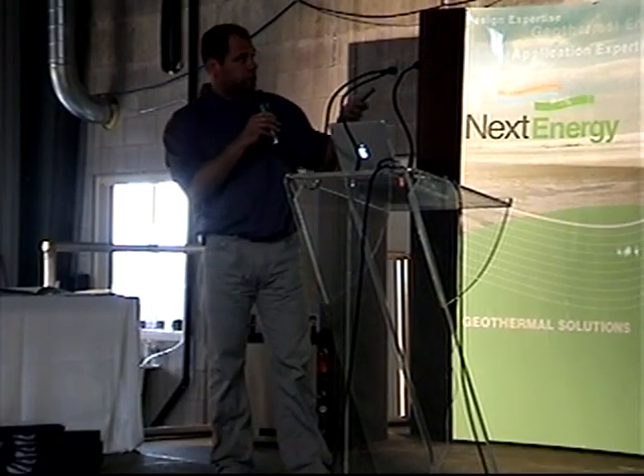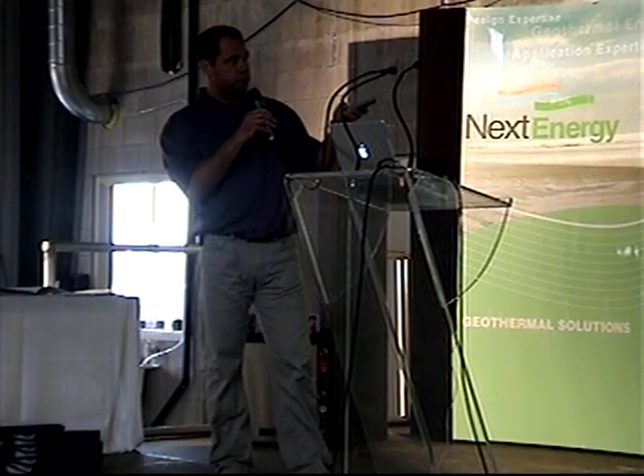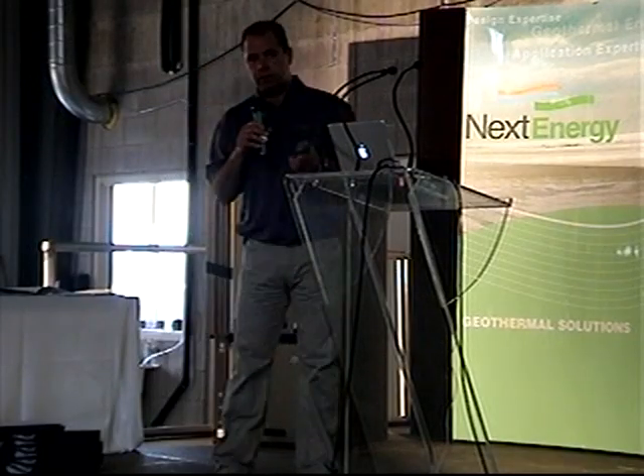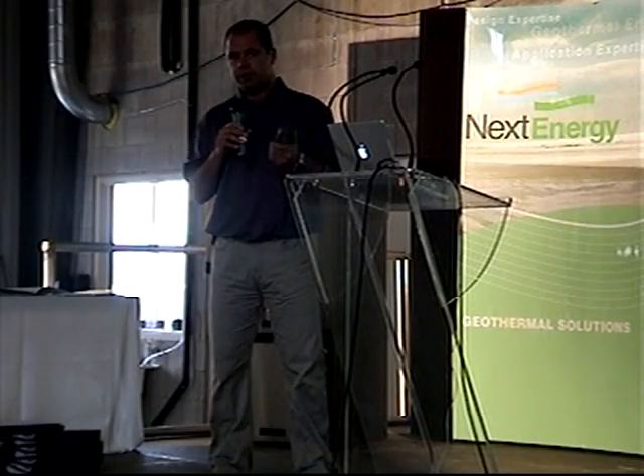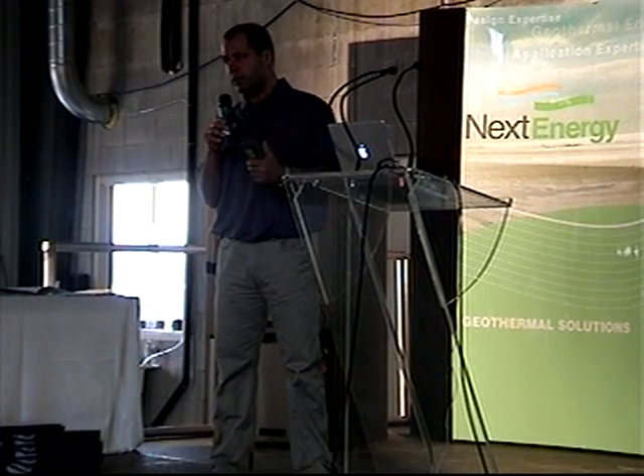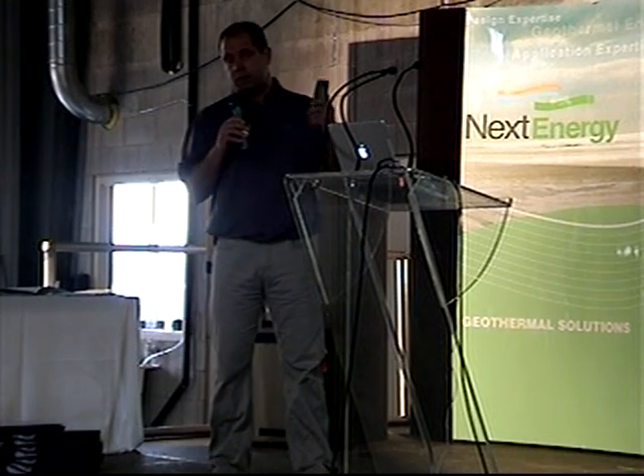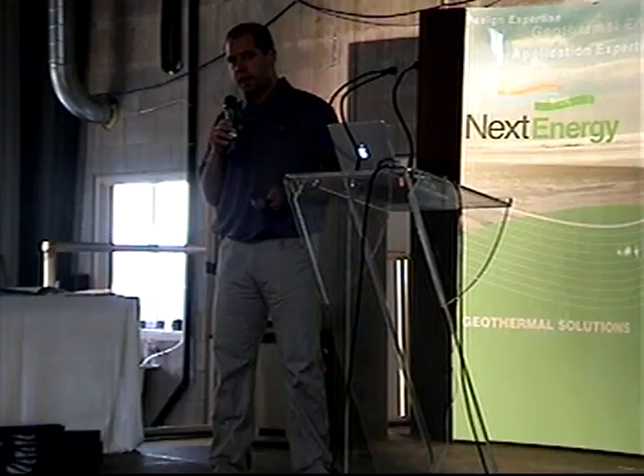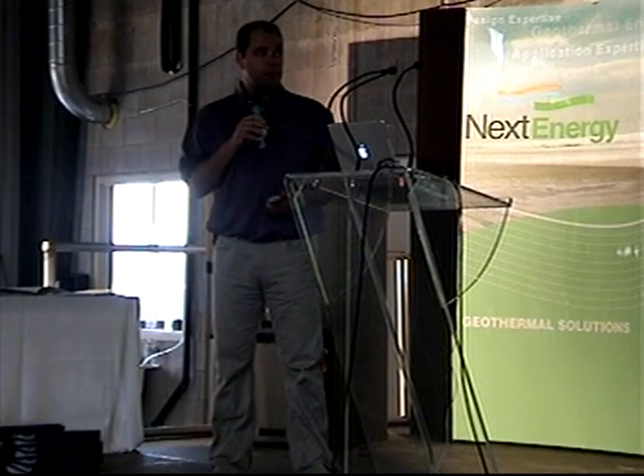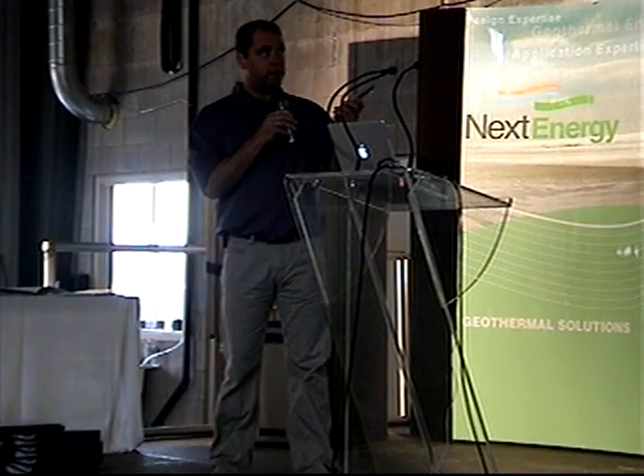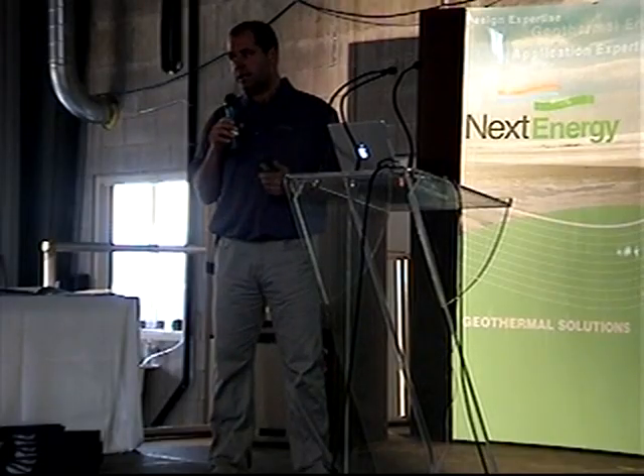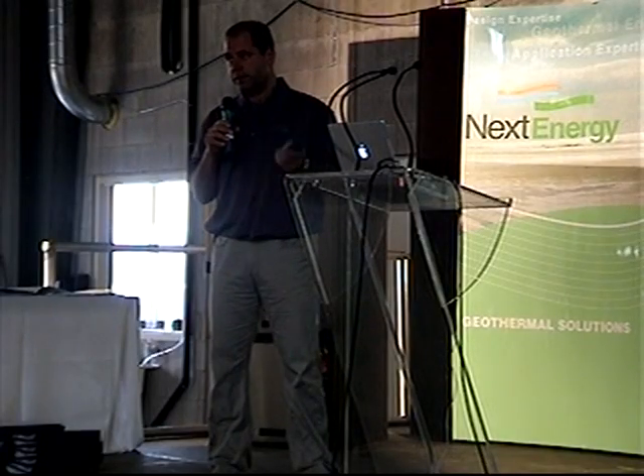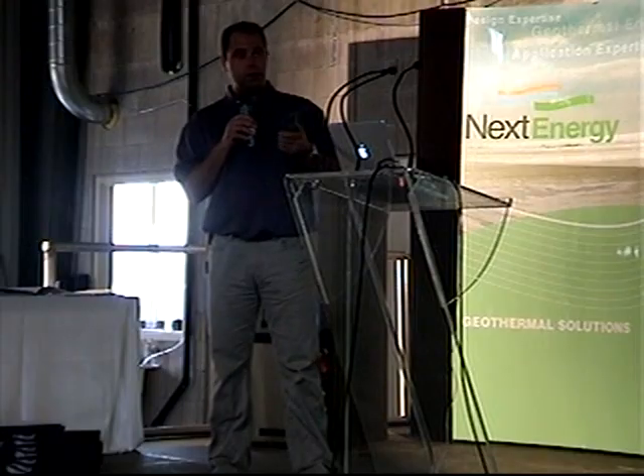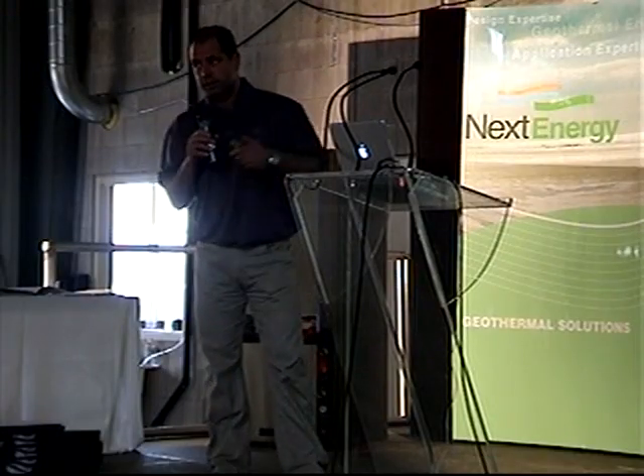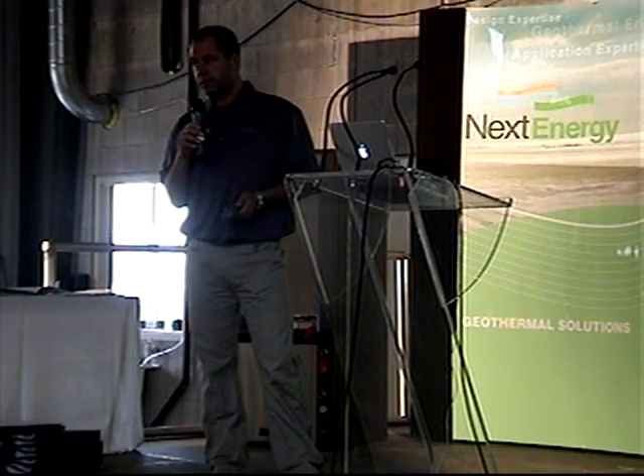Okay, again, higher pressures. Now, lower discharge temperatures. I don't know if any of you guys have noticed on the new units for the desuperheater, there's actually a thermostat on the discharge line that's wired in series with the desuperheater pump. The reason for that is with 410, the discharge line can run at a low enough temperature that if you try to desuperheat, you can actually take heat from the water heater and put it back into the refrigerant.